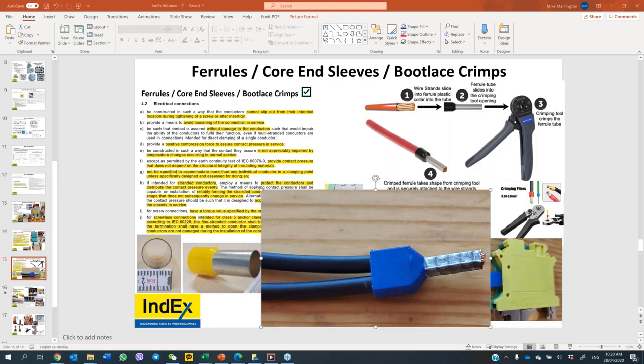Is it allowed to cut off the extra copper strands from the end of the bootlace? My personal way of doing it is I make the strands go further so that you make sure you have 100% coverage within the crimped area. And then, yeah, use a small set of sharp side cutters and cut it down, because sometimes ferrules are too long. You can cut them down depending on the terminal type. Not all terminals have the same terminal depth into them.